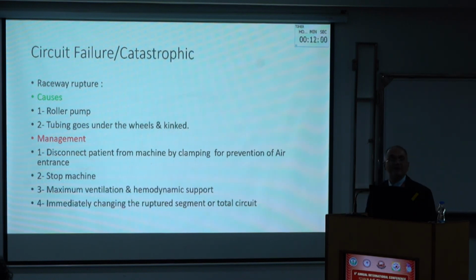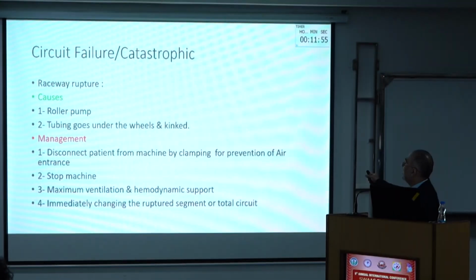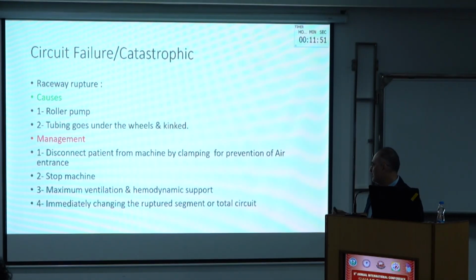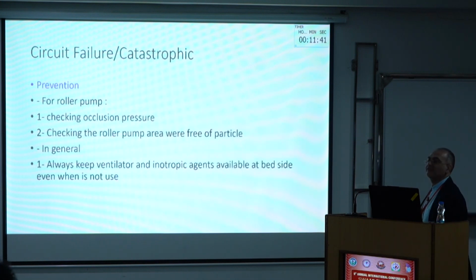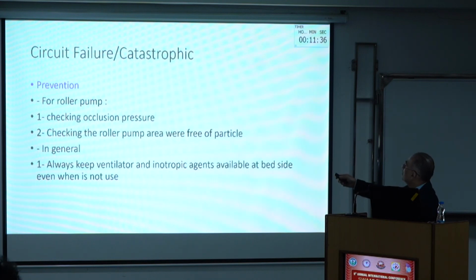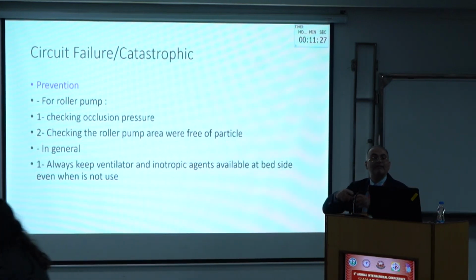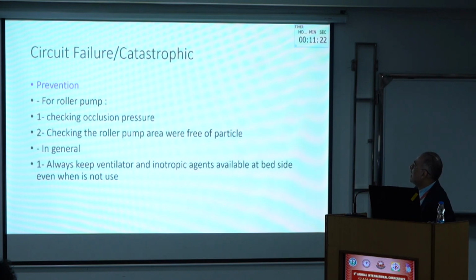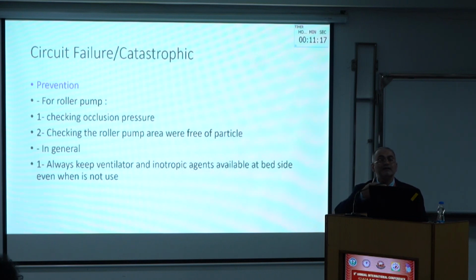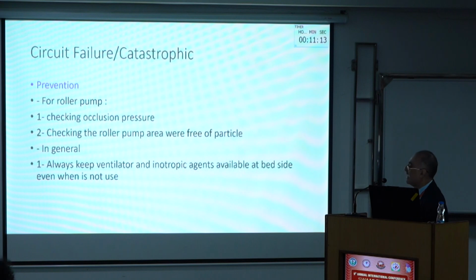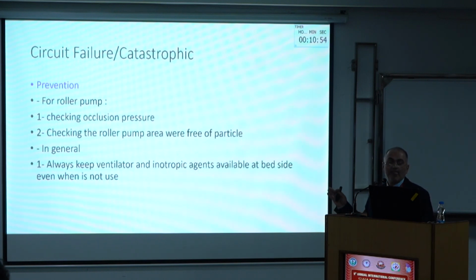What we can do in the management of such a catastrophic happening in our patients is disconnect the patient by clamping, stop the machine, give maximum ventilation and hemodynamic support, and immediately change the ruptured segment or the total circuit if needed. How can we prevent this disaster? For the roller pump, check the occlusion pressure and check that the roller pump area is free of particles, like the broken glass that sometimes goes inside the roller pump and may even rupture your system. And in general, a notice: you should keep the ventilator and inotropic agents available at the bedside, because you don't know what will happen in the next minute for your patient. Therefore, don't keep the ventilator or the inotropic agents away from your patient. Always keep them at the bedside to better cover your patient in a catastrophic event.